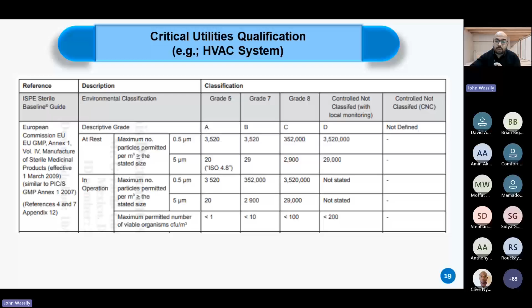The same applies for all the grades, but here I want to draw your attention to a very important point: upon increasing the cleanliness grade from C to B to A, going to the A, this is the highest level of cleanliness grade, and this is actually where the vaccine filling takes place. And you can see here that under grade A, we are having the least number of allowed particle concentration for the size of 0.5 and 5 micron. Okay, so by qualifying the HVAC system, I will be releasing the HVAC system for routine use and routine operation with a high degree and level of assurance that it will enable me to have a clean room with the needed cleanliness grade.